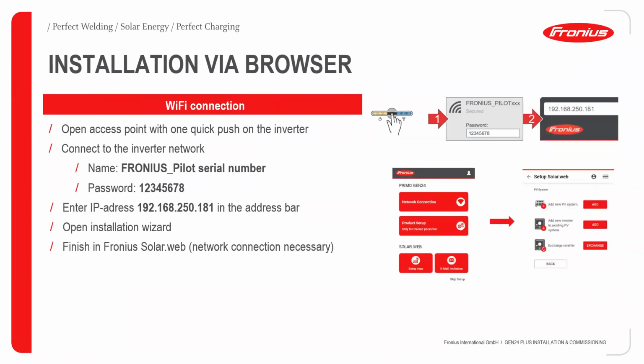The other way you can achieve this is via the web browser. This might be too technical, but it's quite straightforward: open the Wi-Fi access point, locate the Fronius inverter, log on to the Wi-Fi of the inverter using the provided password, and then on the web browser input the IP address. Once that's done, it will automatically take you to the installation wizard where you can continue with your commissioning process.